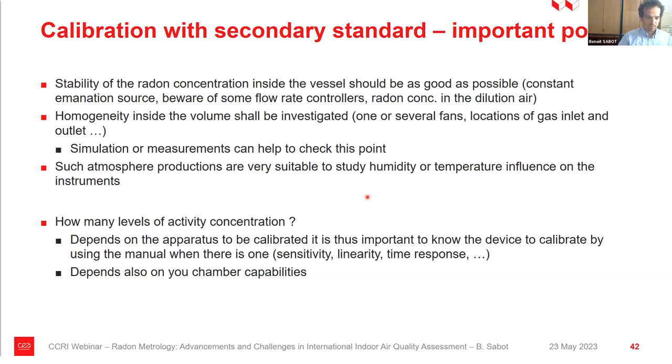What you have to find at the end is what are the best points of calibration in terms of activity concentration. It may depend on the rules, as I said, but it may depend also on the apparatus to calibrate. And what I learned is that sometimes it can be very difficult because you have a new device to calibrate, and sometimes there is not much detail about the device. So you need to understand how it works to make sure you will calibrate it properly in the right range, that you will find the time response of the device, and that you will make sure that you have measured the linearity part of the device and other problems.